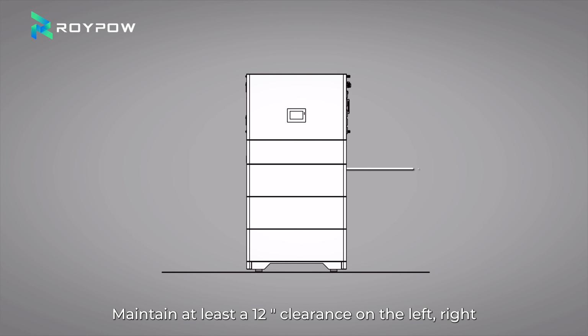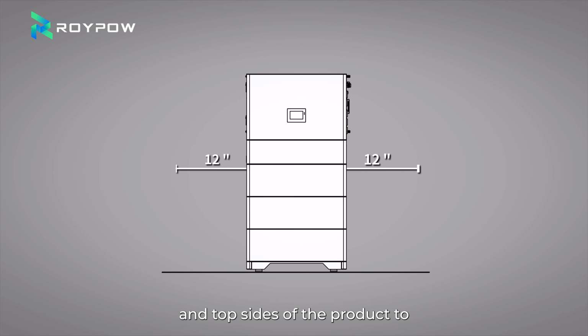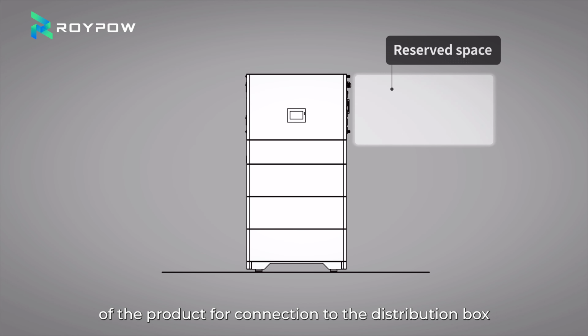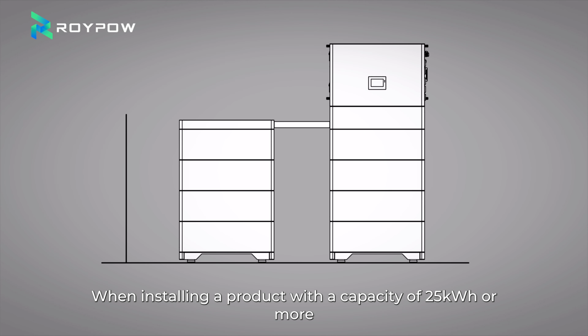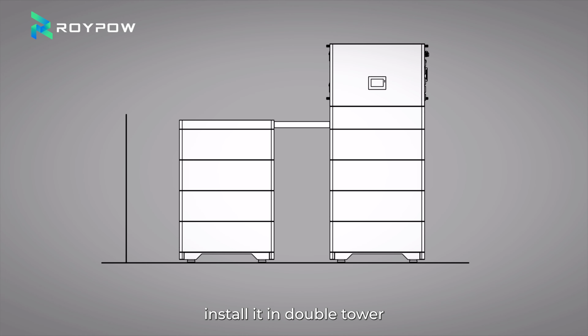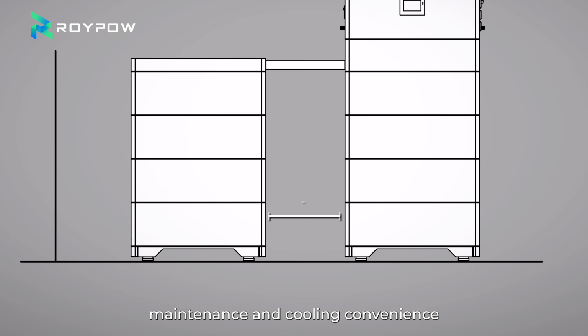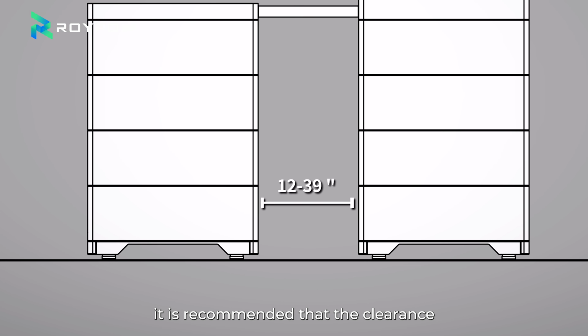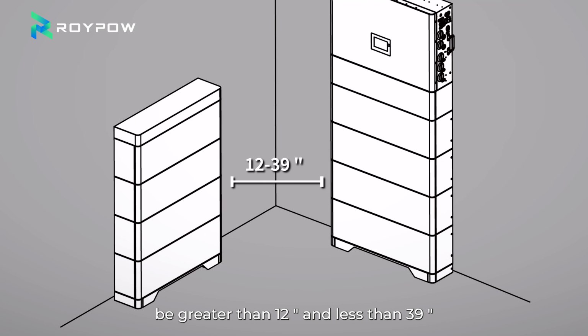Maintain at least a 12-inch clearance on the left, right, and top sides of the product to ensure adequate ventilation for cooling. Ensure there is enough space on the right side of the product for connection to the distribution box. When installing a product with a capacity of 25 kilowatt-hours or more, install it in double tower. For installation, maintenance and cooling convenience, it is recommended that the clearance between battery clusters be greater than 12 inches and less than 39 inches.